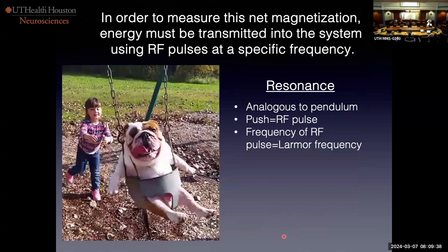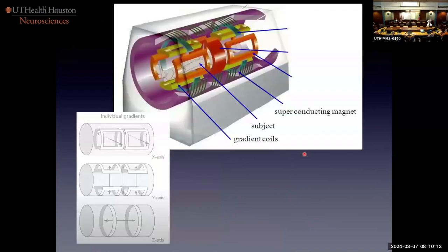So far I've done nothing to create an image. I've got to put energy in and then listen for the signal that comes back to figure out what the tissue is composed of. This happens by resonance. The analogy is if you're pushing a swing at exactly the right frequency, there's an optimal transfer of energy — that's called resonance, a natural phenomenon. The frequency of the pulse we put in is at the Larmor frequency. Let's look for a second at what's inside the magnet.